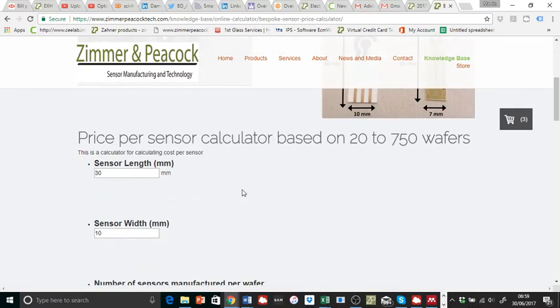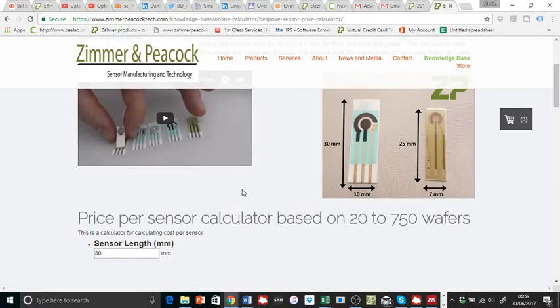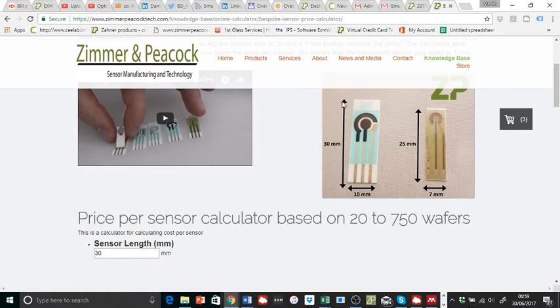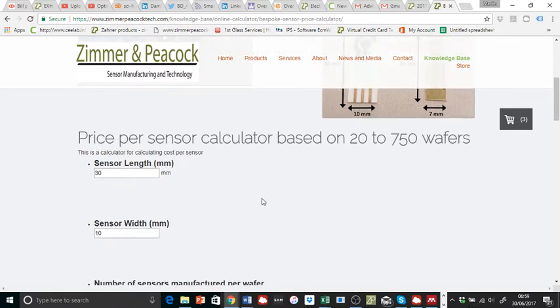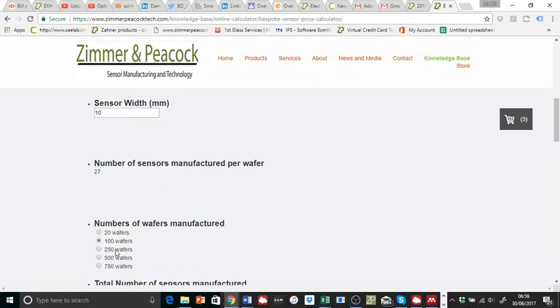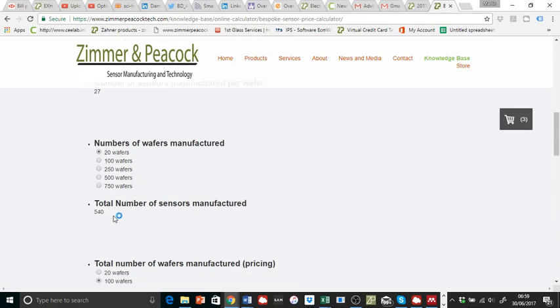I'm going to specifically deal with the number of 300 sensors required. Our standard sensors at Zimmer and Peacock are 30 millimeters by 10 millimeters. If I use that 30 millimeters by 10 millimeters per wafer, that will produce 27 sensors. Now, if I run 20 wafers, that's going to produce 540 sensors.